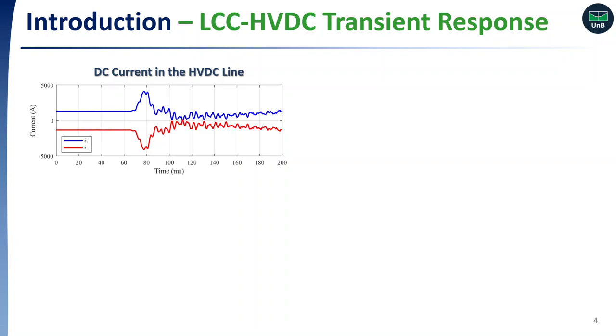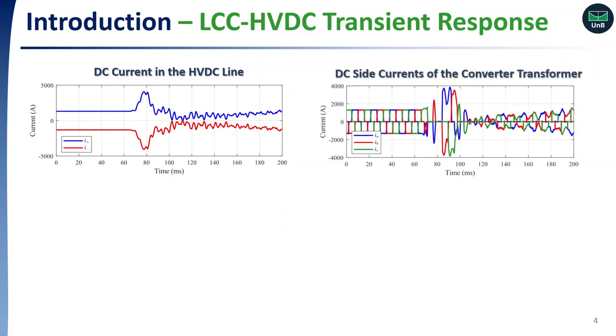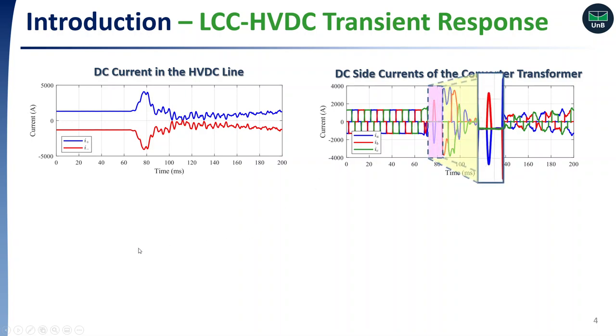For example, these are the currents on the DC side of the Y-delta converter transformer. As one can see, during commutation failures, a converter valve that is supposed to turn off continues to conduct, such that the current is not transferred to the next valve in the firing sequence. As a consequence, there is a momentary interruption of the power transmission through the link, leading the disturbance to be aggravated.